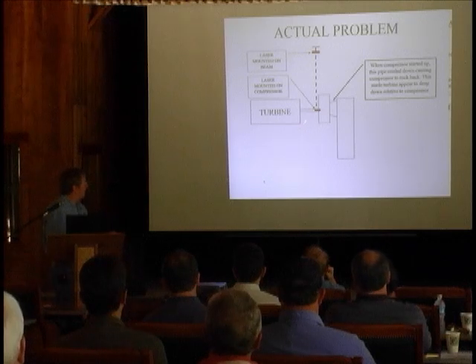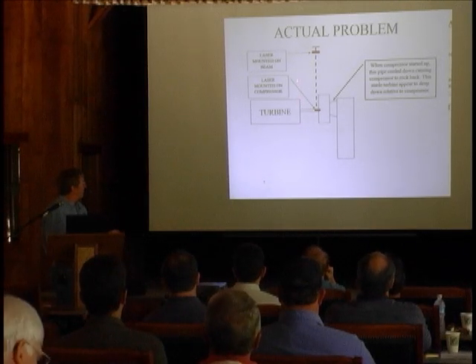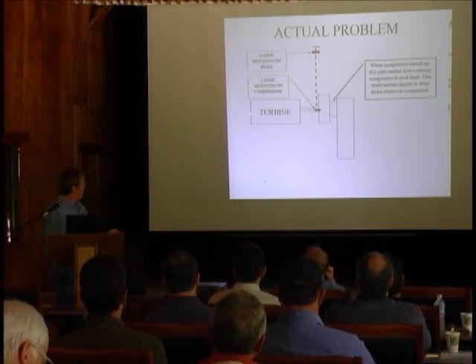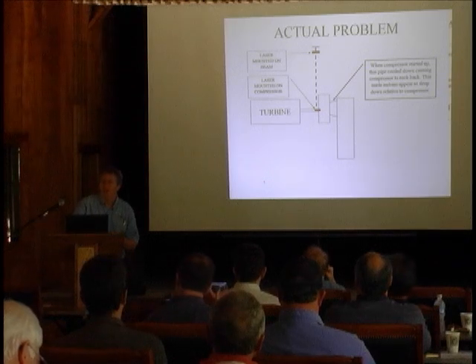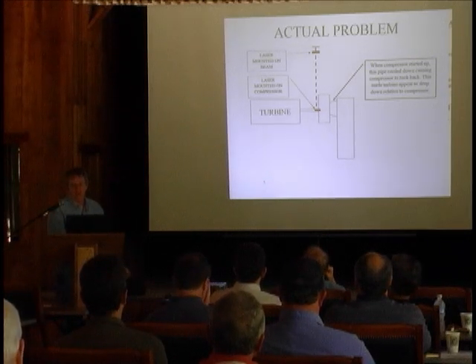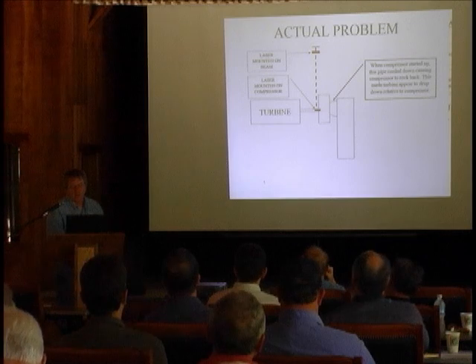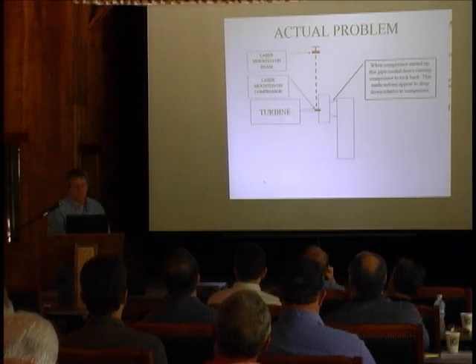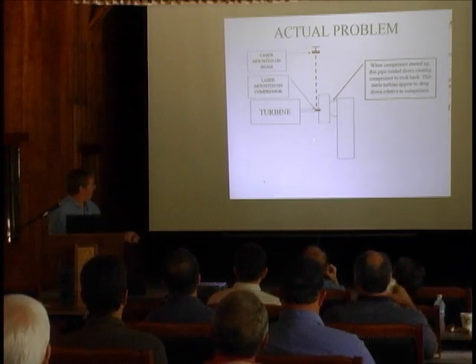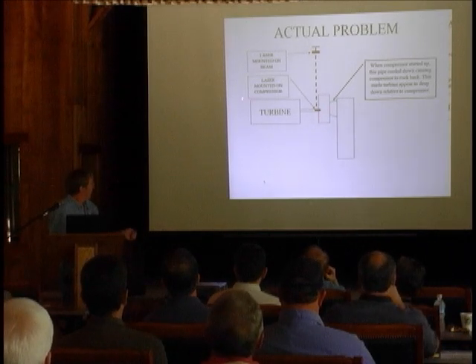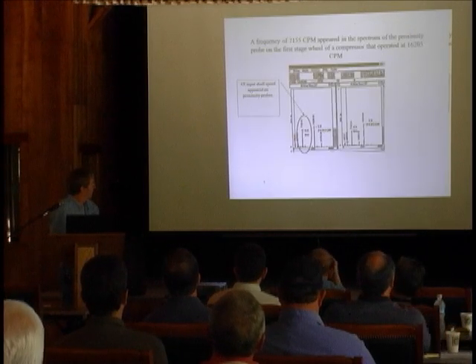So what I finally had to do, I actually took the turbine and I had to set the turbine in the air, the back end of the turbine, 120 thousandths high. And they've run like this. They always have me come in and align that thing. And again, the manufacturer's alignment recommendations were entirely wrong because they had no way of knowing this was happening. And you have to set it up high. Okay.